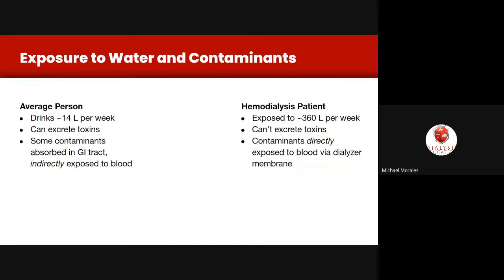Our patients' kidneys don't work, so they can't excrete toxins. Unlike drinking, dialysate water is directly exposed to the blood via the dialyzer membrane — there is no gut to absorb or prevent contaminants from reaching the blood. That high volume, the inability to excrete toxins, and direct blood exposure make dialysate and water purity absolutely critical.